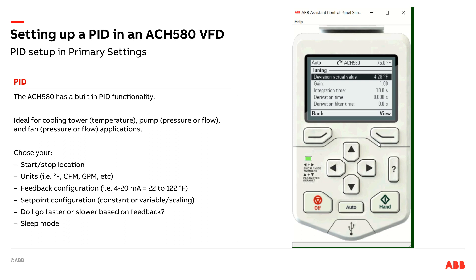Now I've got my tuning. One thing I like is on this screen, this value here is live — it's telling me how far my actual value is away from set point. I'm a little over four degrees higher than my set point right now. I've got my gain, or P; I've got my integration, my I; and if you really want to tune it in, you've got a D to play with. But in most cases, the gain and the integration are the only ones you're adjusting.